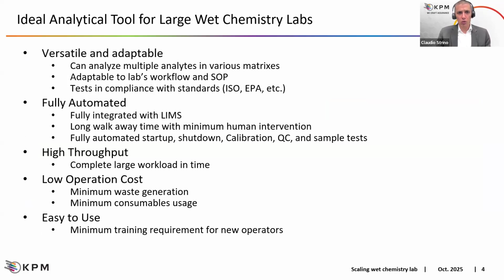What is the ideal tool we could use to cover large volume labs? The instrument should be versatile and be able to adapt itself. It means analyze multiple analytes in various matrices, be able to follow and easily fit in the lab workflow and SOP, so that all the tests are in compliance with the main regulations, for example ISO, EPA. The tool should be fully automated, so it means fully integrated with LIMS, long walk-away time with minimum human intervention, fully automated startup, shutdown, calibration, QC, and sample test. The tool should be able to cover the high throughput, so complete large volumes in time.